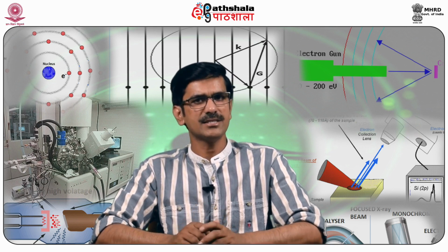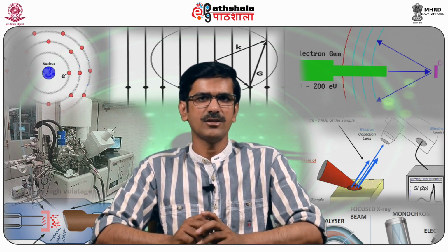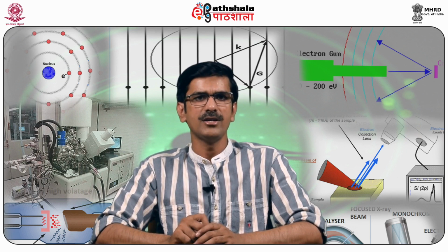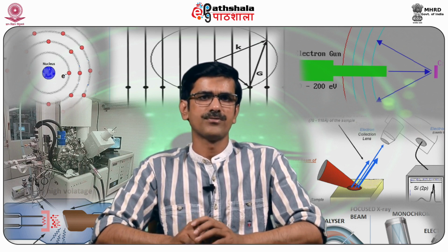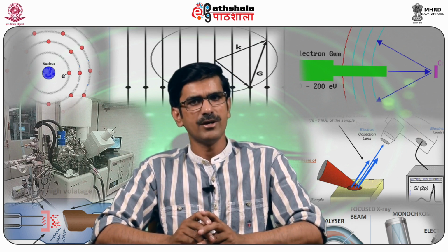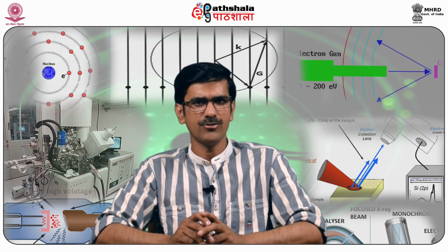These lines are intense, sufficiently energetic to eject electrons from the lesser bound orbitals of most molecules, and have a small natural width of only a few millivolts. Other sources used are helium-2, helium-1, neon and argon-1.